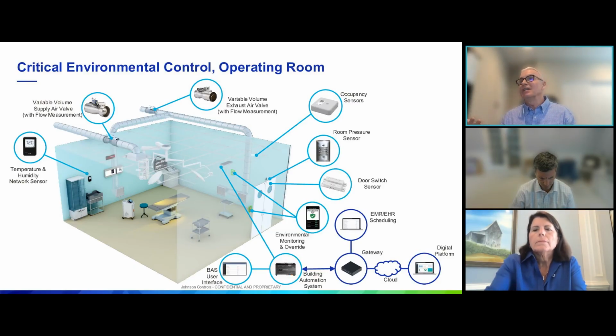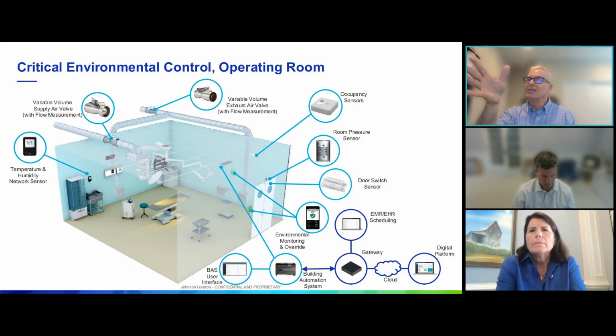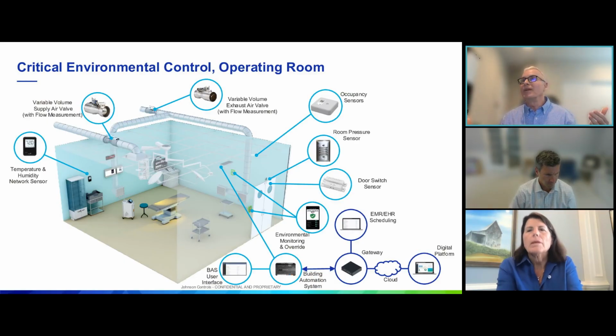And that could be a little bit challenging in itself as well, because we want to make sure that we're not getting to a condition where air can now come in from that hallway back into the space. We want to still make sure that we're achieving that temperature, humidity, and pressure differential, but we also want to make sure that we're scaling back the airflow itself so we're not consuming as much energy. And then, finally, just touching back on Guideline 43, resilience: the OR cannot go down. That is really the situation that we have here. So we need to make sure that all the equipment supporting that OR, all of the mechanical equipment, is in the right running condition, so we're not taking that risk on and having those problems.